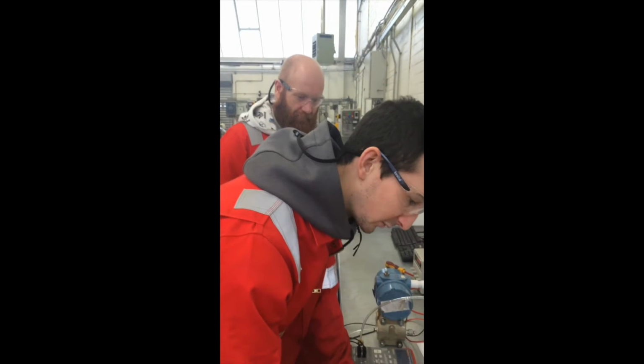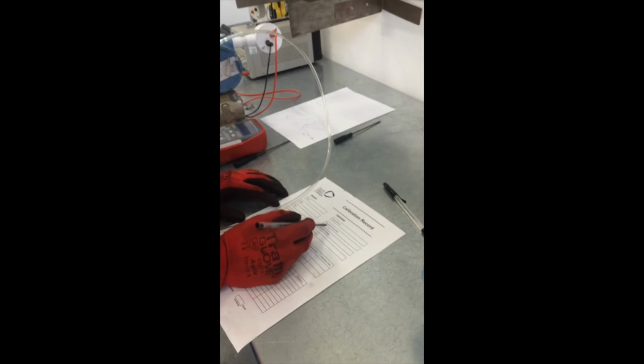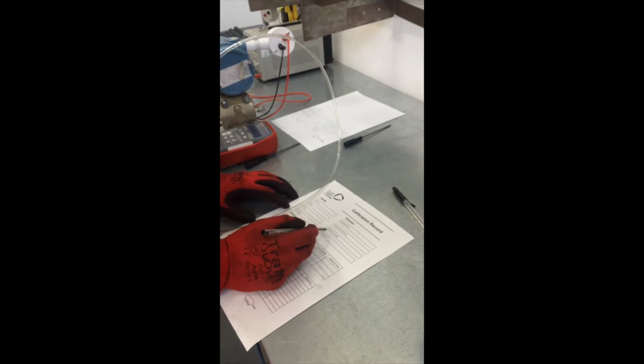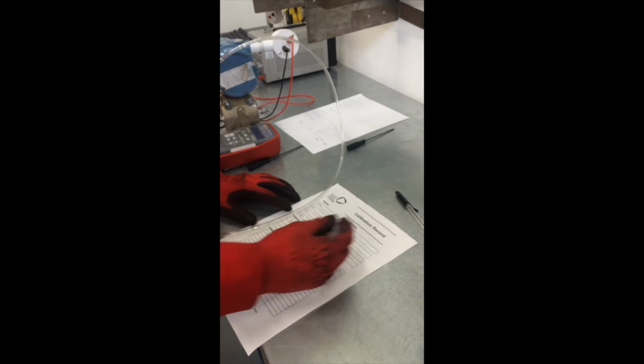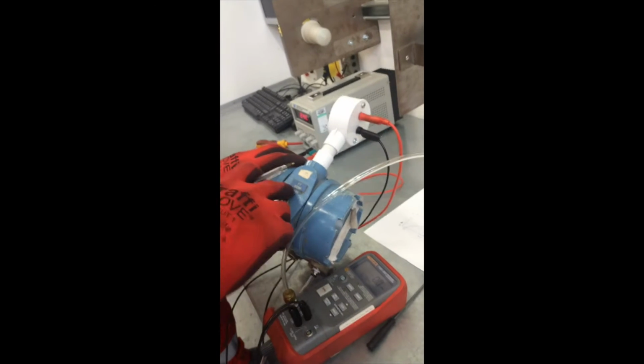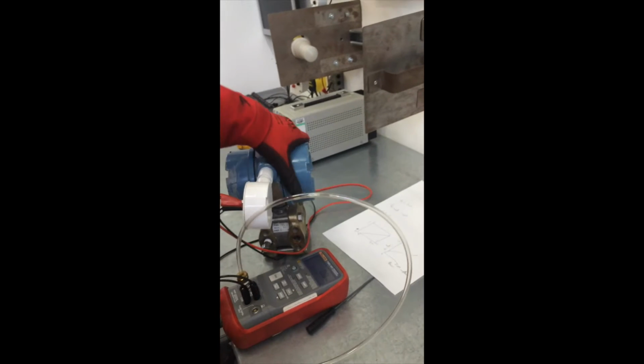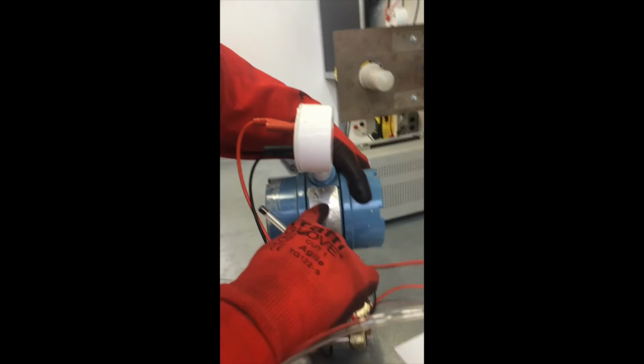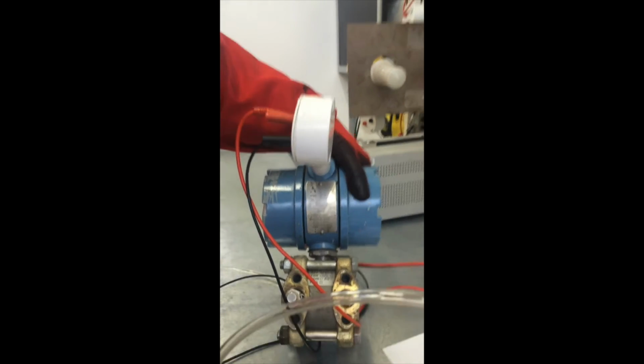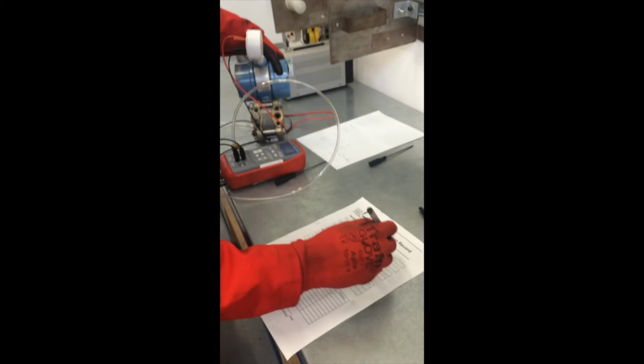What I'm doing here is filling out the calibration record. In this bit it's got the equipment ID, the equipment serial number, the calibration range and the tolerance. So the equipment ID is on the top of your DP cell, and that's it there, so it's FT6296. Then your serial number is on the back here, stamped into the back, so it's ES 7285.